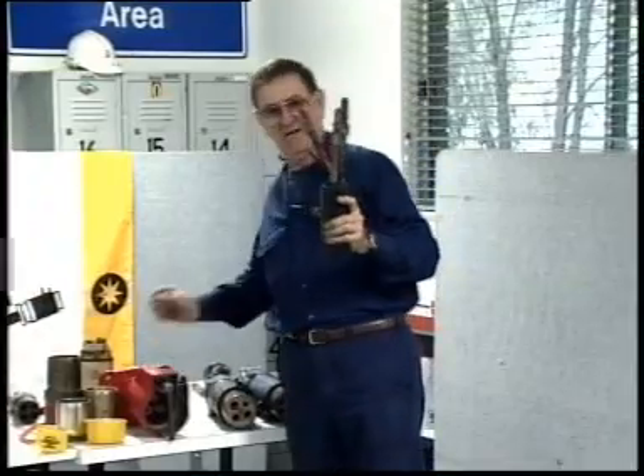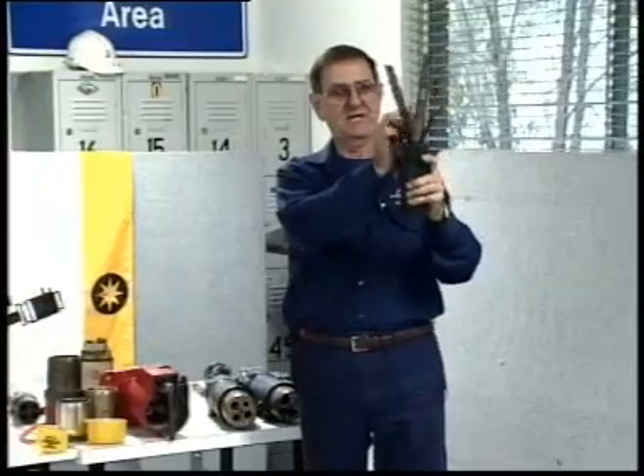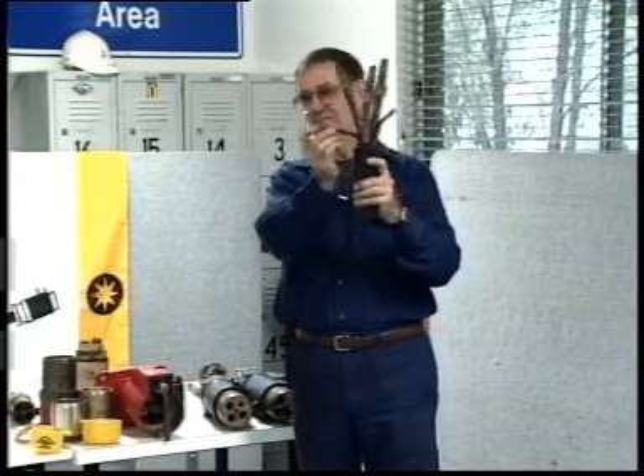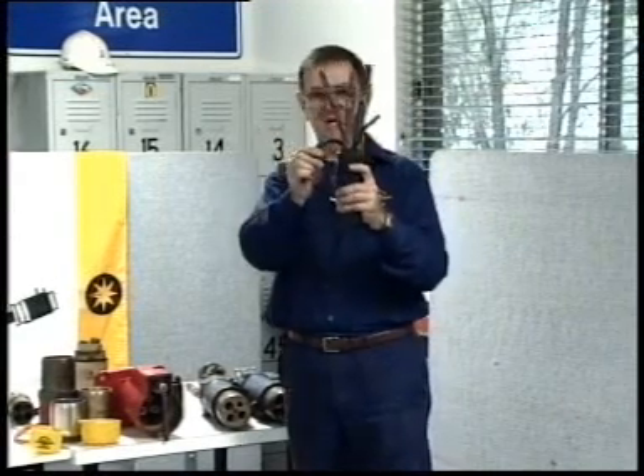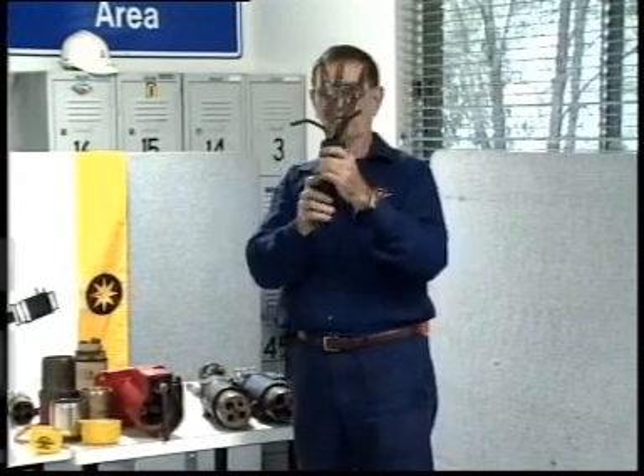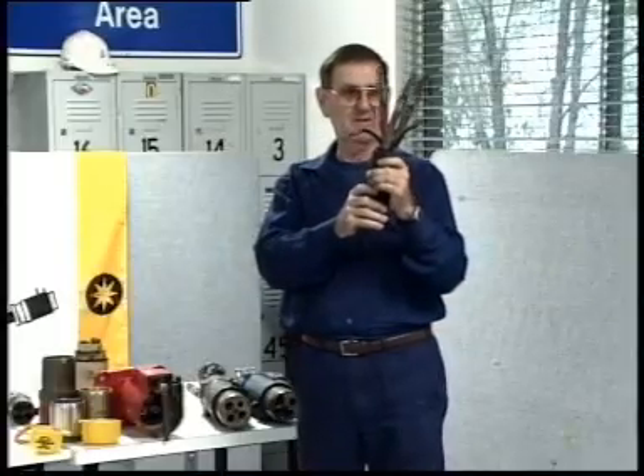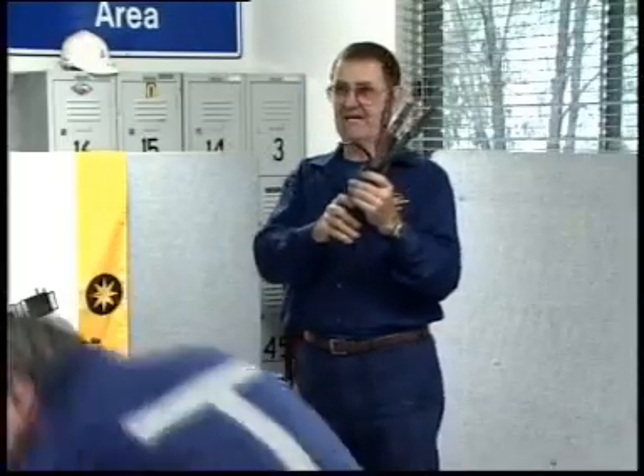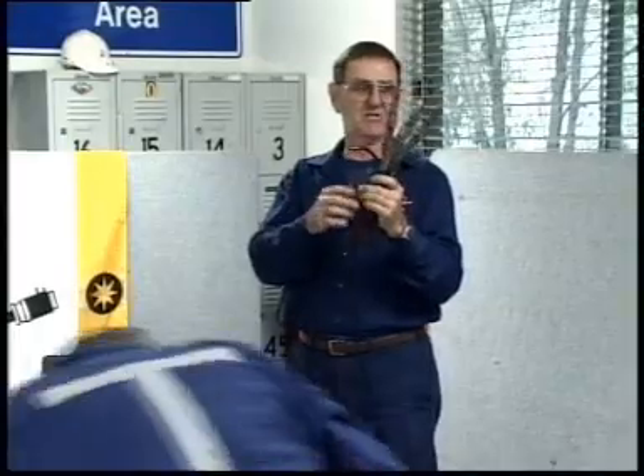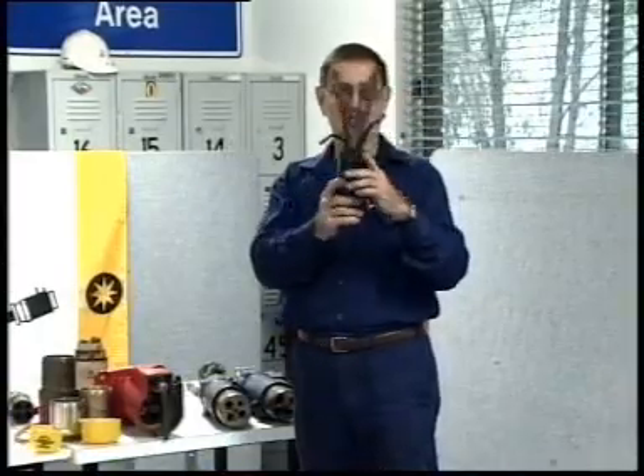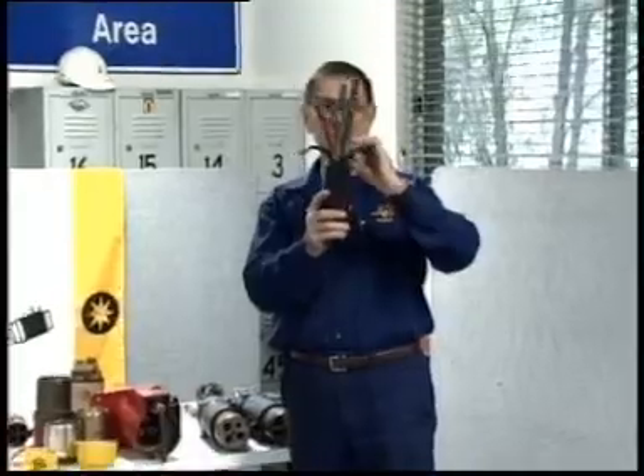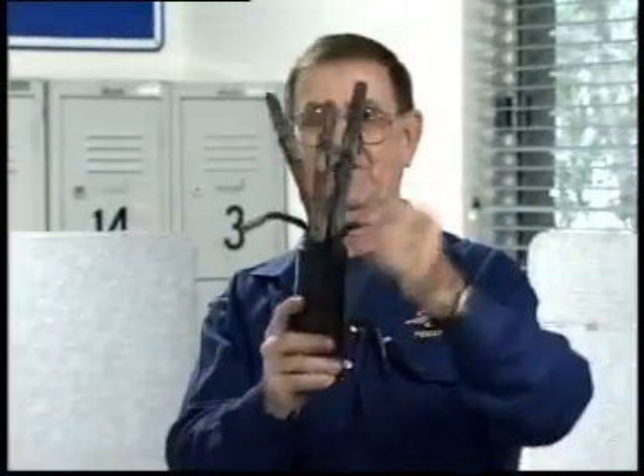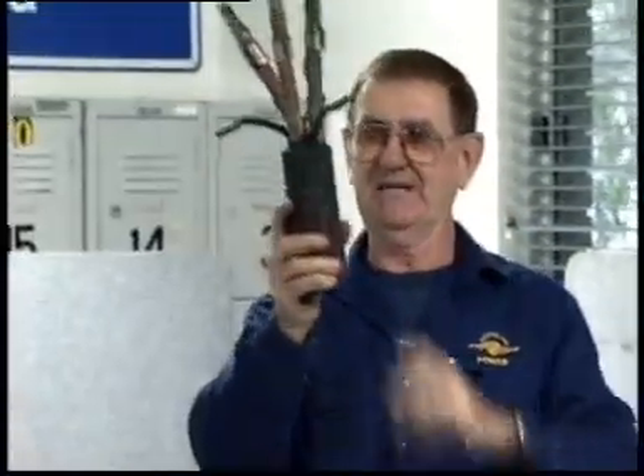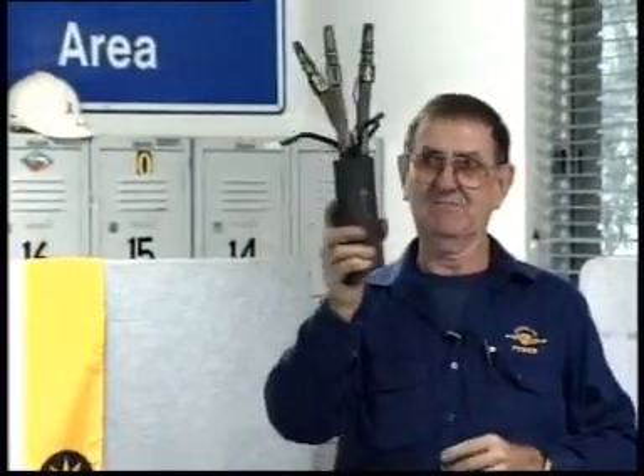The earth wires are made off onto little thimbles at the side here that have a screwed section in them, and they screw onto the side of the body of the plug. This one here is pulled completely out of the back end of a 300 amp plug, and it drew an arc out they consider was 1 to 2 metres long before protection cleared. It snapped off all of the screws and the holes that were holding these on and pulled these all the way through the plug and out the back end. So you can imagine how much damn tension that had on it.